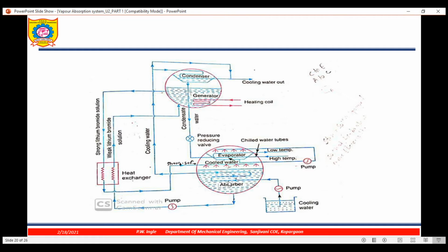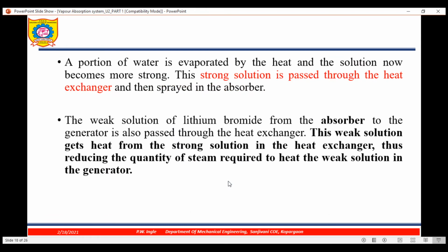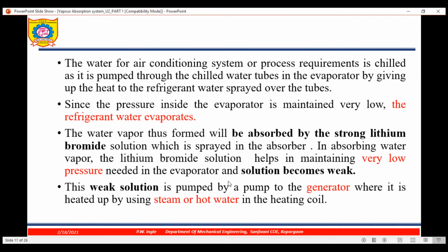Now next, in absorbing the water vapor, the lithium bromide solution helps in maintaining the very low pressure needed in the evaporator, and the solution becomes weak. The LiBr solution has absorbed all the water vapor which acts as a refrigerant, and it forms the weak solution. Now this weak solution is pumped by a pump to the generator where it is heated by steam or hot water in the heating coil.